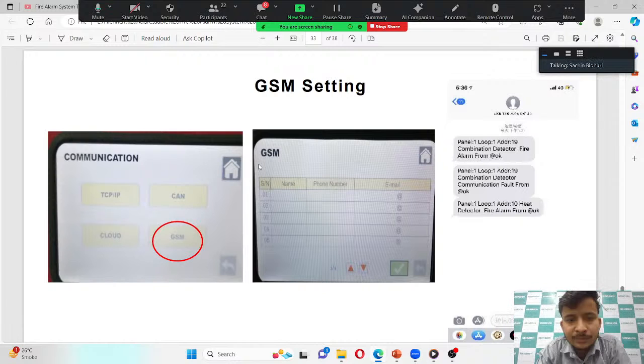Then GSM settings. GSM setting is for providing the alarm or notification to the operator or the security person in the case of fire or fault occurring in the fire alarm panel. In GSM, you can add the name of that person, the phone number, and the email ID of that person, and then just save that. Whatever information you provide here, in case of emergency or alarm, the panel will automatically send a notification to his mobile phone in the form of SMS. So he will get an alarm or notification of that particular event which occurred in the fire alarm panel.